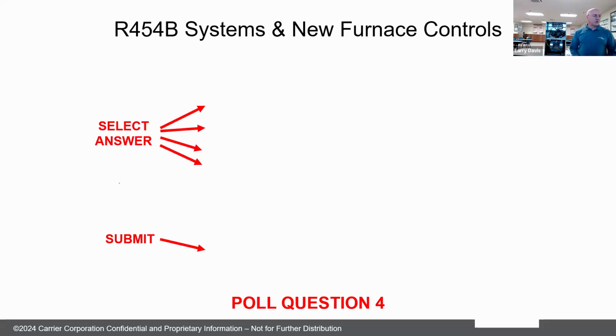All right. So which of these should be considered regarding service items and tools? Best answer is all of the above. Make sure you have plenty of ventilation when you're working in a space. Have a leak detector with you that is rated for use with 454B. Make sure your equipment, vacuum pumps, leak detector, and so on, are 454B compatible, and your gauges as well. It's recommended to have a set dedicated so you're not cross-contaminating. That's no different than now. If you do air conditioning and refrigeration, chances are you have multiple sets of gauges on your truck, depending on what refrigerant you're dealing with. So that's nothing new there. So the best answer is all of the above. We'll stop sharing that. Good deal.